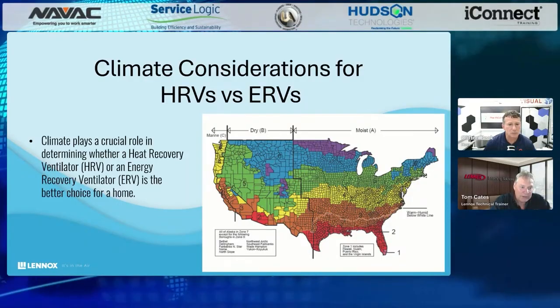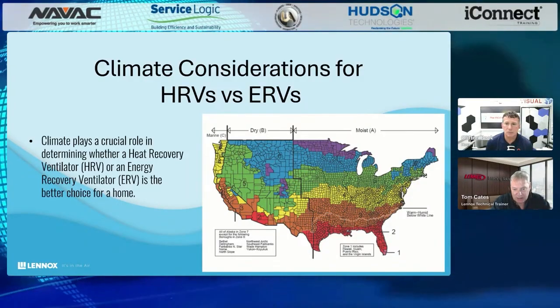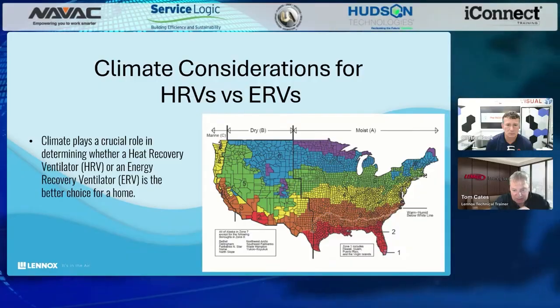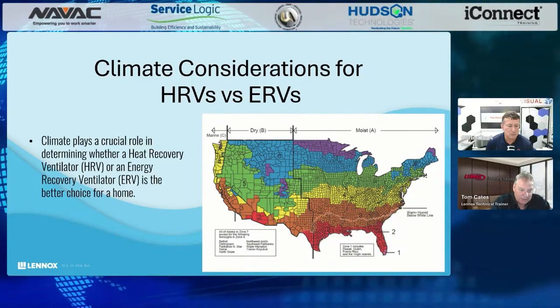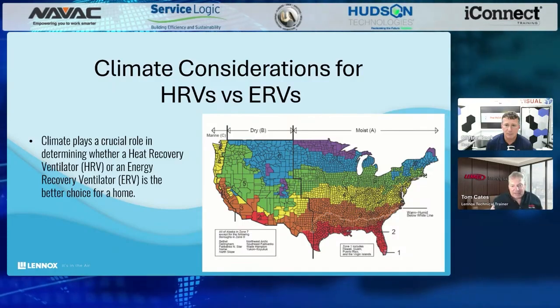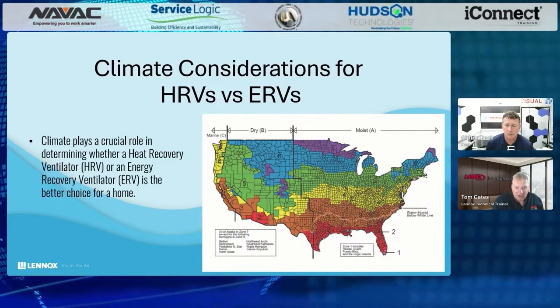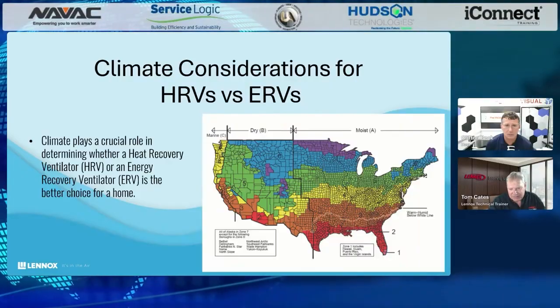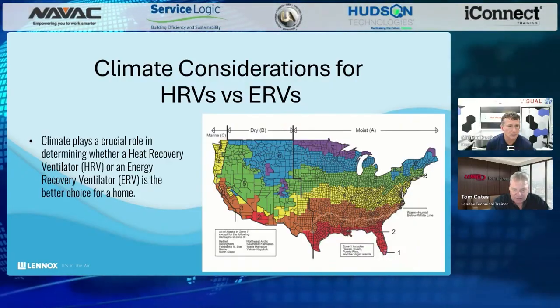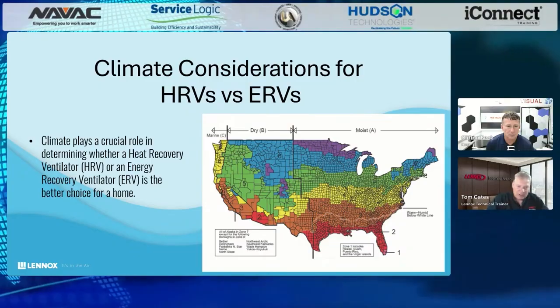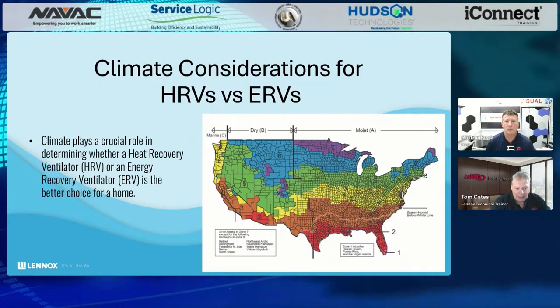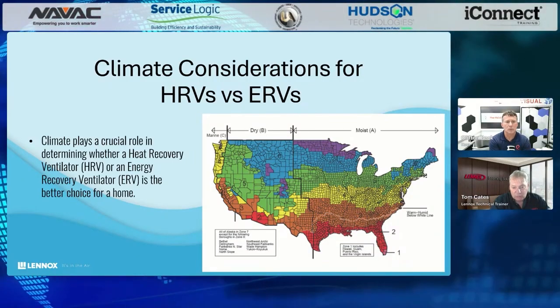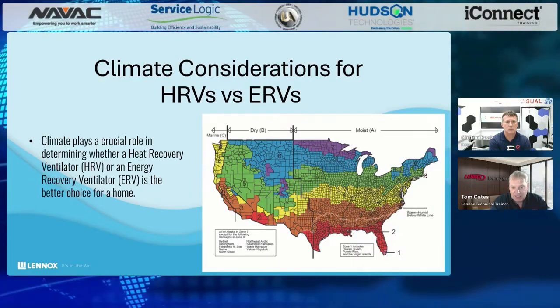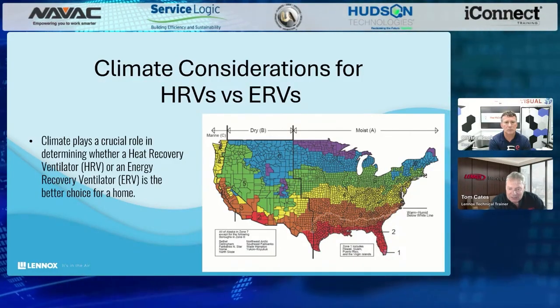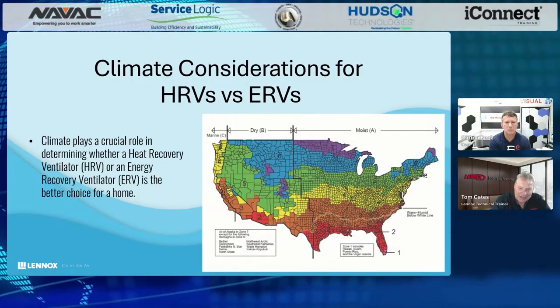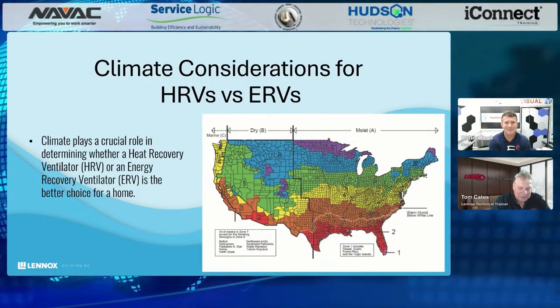Now, when we talk about the use of an ERV or an HRV, it's going to be influenced by the moisture content of the outdoor air. Am I in a dry area or a moist area? This is a nice simple map that breaks up the US into a dry zone area and a moisture zone area, because exterior moisture will play a factor as to whether I'm going to use an HRV or an ERV. I'm maybe already giving away where I'll end up at the end of this presentation as to what the actual difference is.